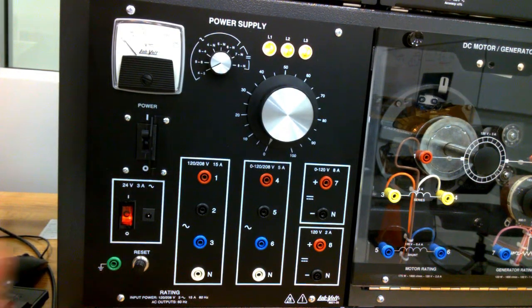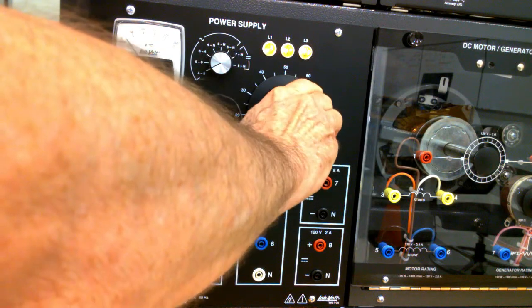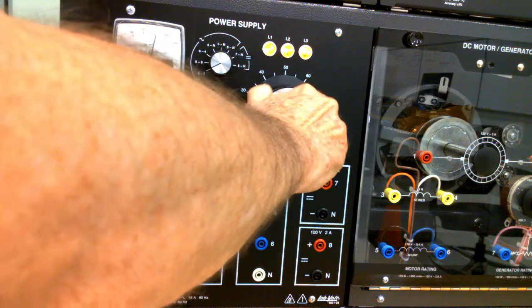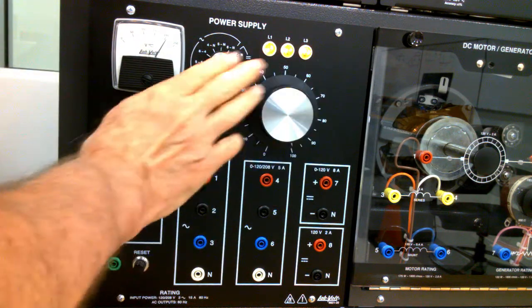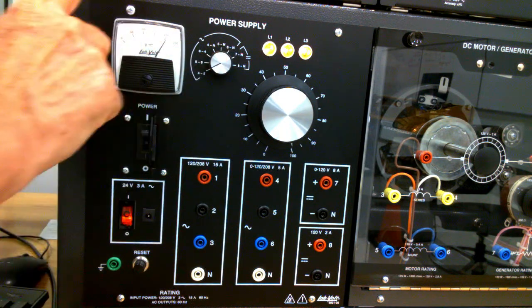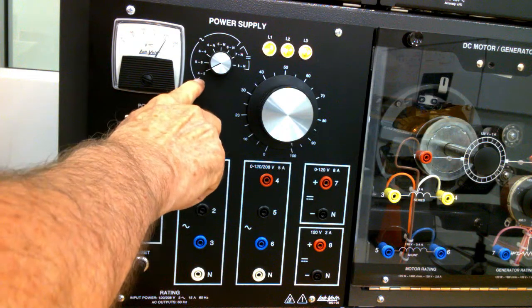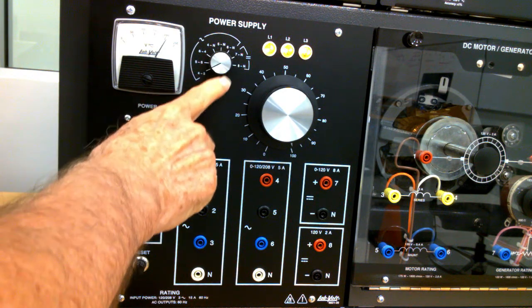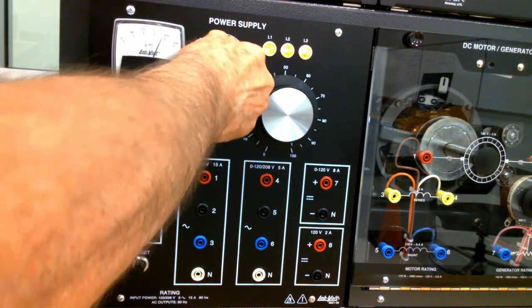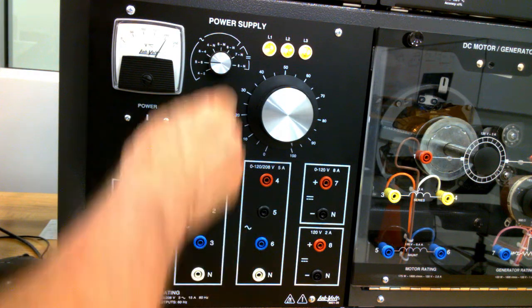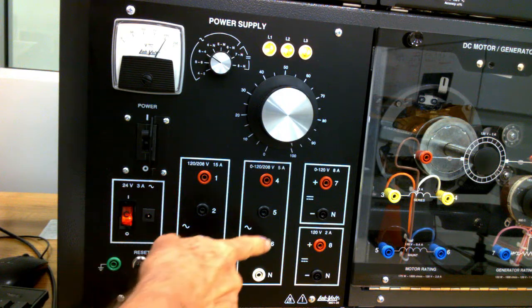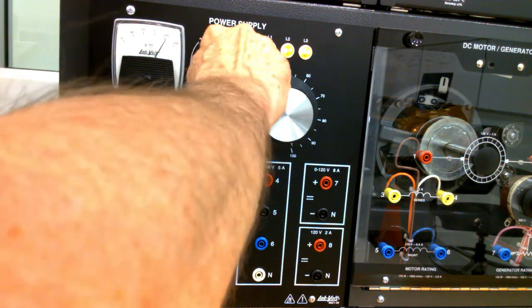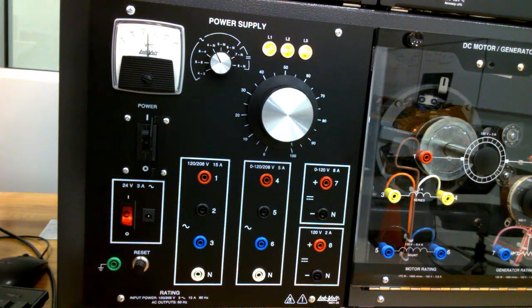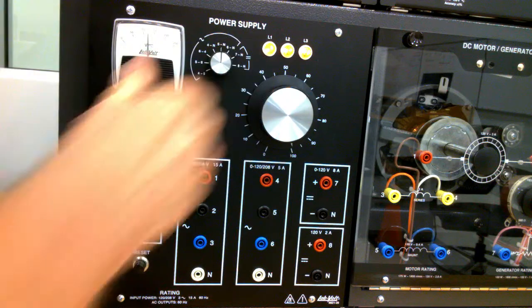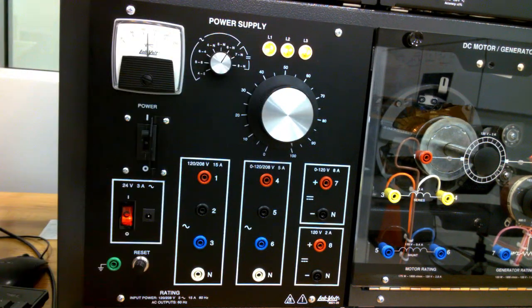Okay, you'll notice as I turn it, if you watch this meter, I can run it all the way up to 208 volts. The switch here is a selector switch for the meter. Right now it is looking at terminal 4 with respect to 5. This is terminal 5 with respect to 6, and this is terminal 6 with respect to 4. If I keep going, I get to see my 120 volt values. This is terminal 4 with respect to neutral, terminal 5 with respect to neutral, terminal 6 with respect to neutral.